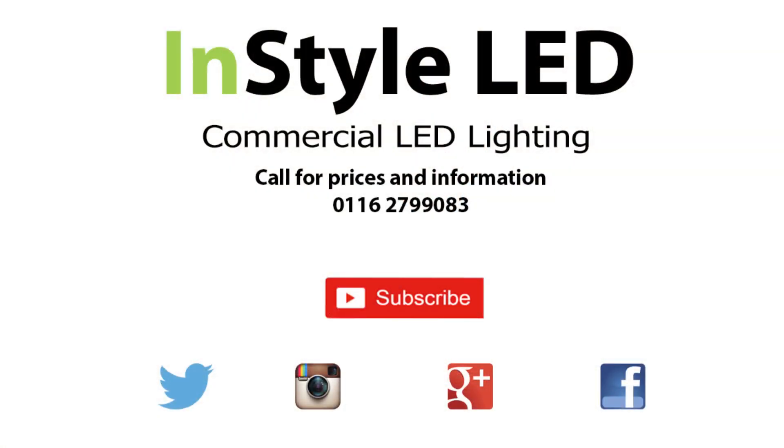Instead, if you run five-core cable from each area back to one central power supply and one receiver, everything can be controlled from one remote and you're only paying for one receiver — potentially saving hundreds of pounds. So it's well worth giving us a call or sending an email. Check out instyleled.co.uk, comment away, and thank you very much.